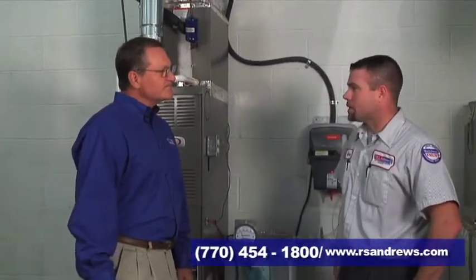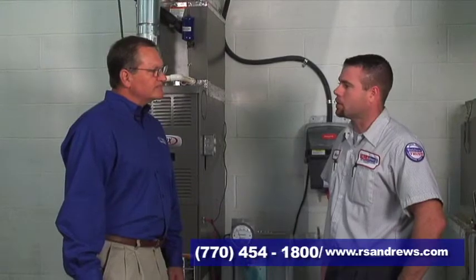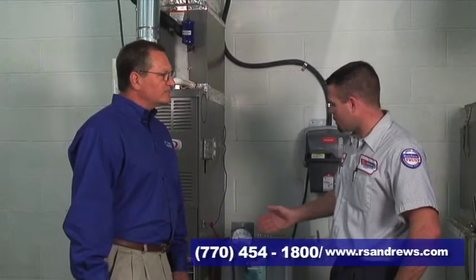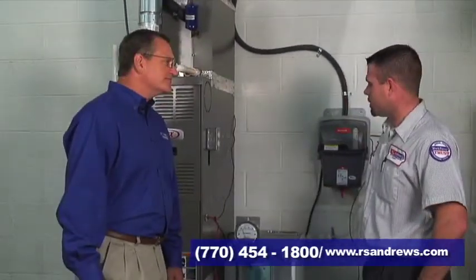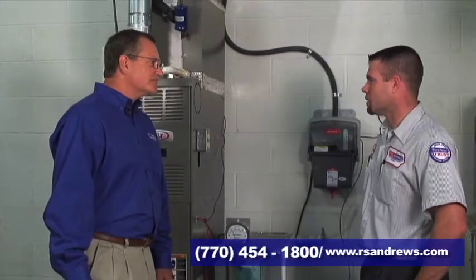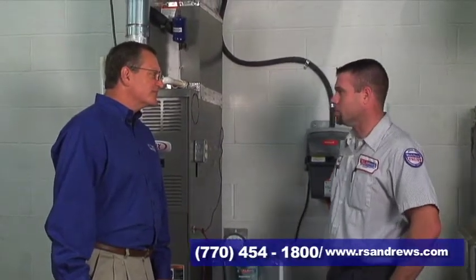Okay. We have equipment that can gauge how hard the blower motor has to work to move air through the system. This right here is a Magnehelic gauge, and it tells me how much pressure is inside the ductwork that the blower motor has to overcome to move air through it.